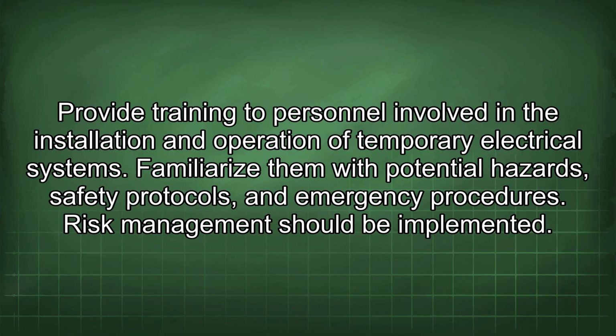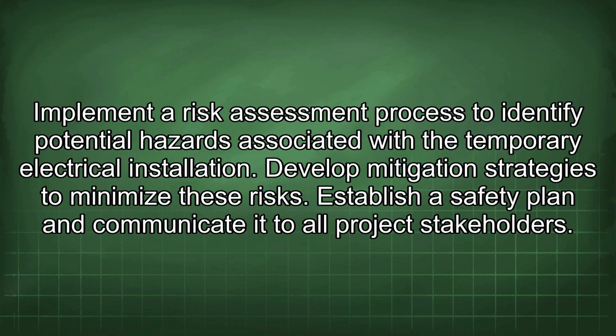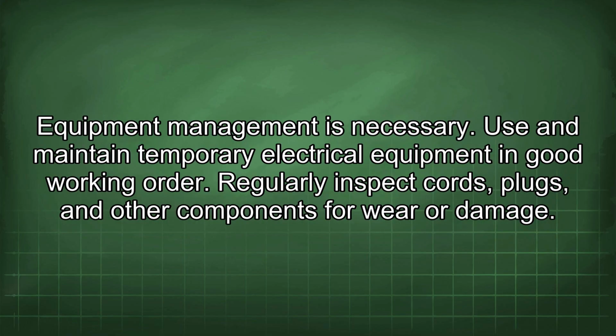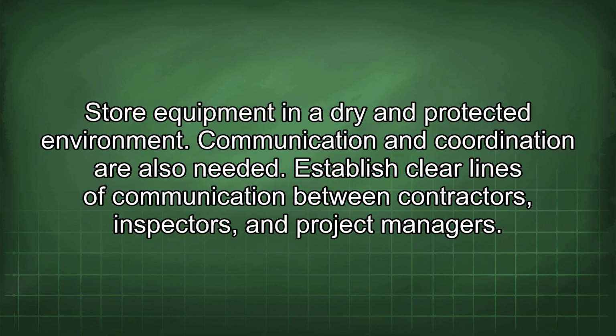Risk management should be implemented. Implement a risk assessment process to identify potential hazards associated with the temporary electrical installation. Develop mitigation strategies to minimize these risks. Establish a safety plan and communicate it to all project stakeholders. Equipment management is necessary. Use and maintain temporary electrical equipment in good working order. Regularly inspect cords, plugs, and other components for wear or damage. Store equipment in a dry and protected environment.